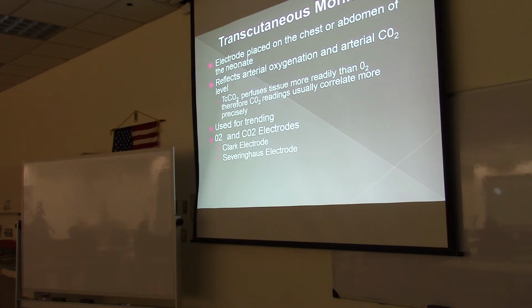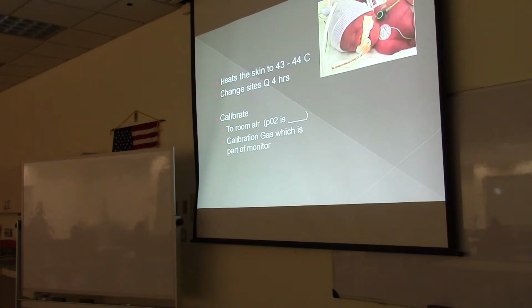And inside the transcutaneous monitor electrode, you've got the same thing you've got inside of a blood gas machine, where you've got a Clark electrode for the oxygen and the Severinghaus electrode for CO2. So it heats the skin to 43 to 44 degrees Celsius, and that could burn neonatal skin if it's on for several hours. So that's the reason that the site has to be changed every 4 hours.